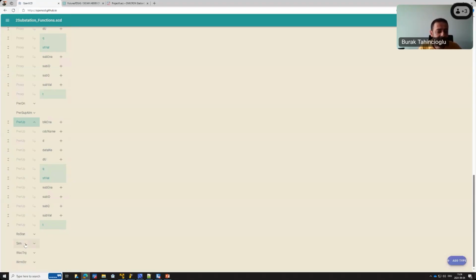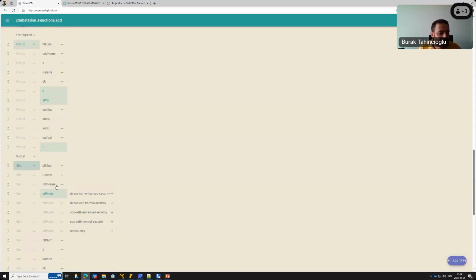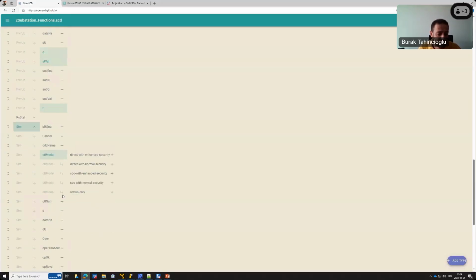The simulation flag, Sim, allows us to receive simulated values or not. Based on the simulation status, we can decide whether we receive a GOOSE or sampled values simulated by a test device, or a value from a process device like a merging unit. We can add this — it wasn't grayed out because Sim is not mandatory in the standard, but we would definitely like to have it.